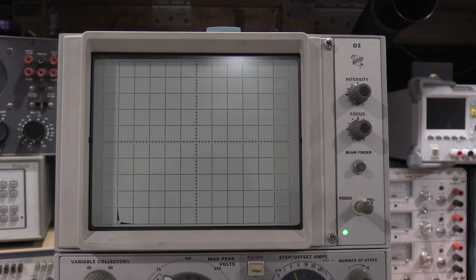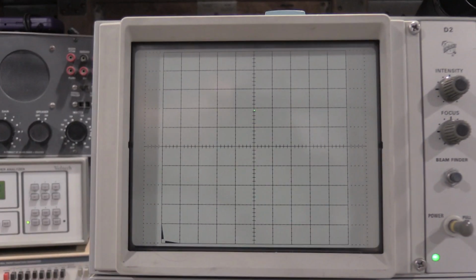Step 13 is adjusting the horizontal compensation. It specifically says not to do this unless it's out of tolerance. Given what's happened with the other adjustments, I'm actually going to leave that one alone unless it proves to be troublesome later. So that moves us on to step 14, which is the step generator polarity balance, pulse 0 and step 0.